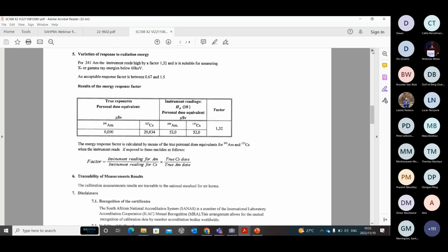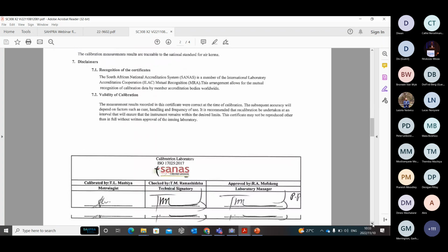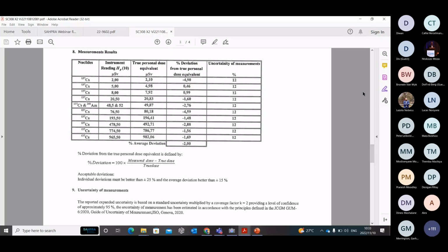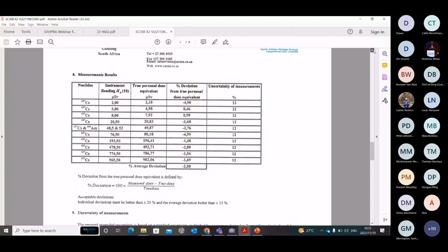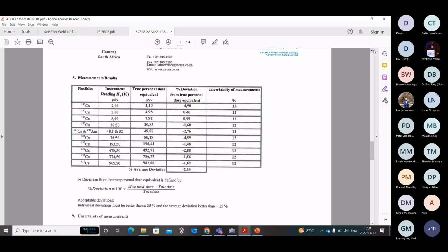Scroll to the next page, to the next table. Okay, thank you. Scroll a bit down. Thank you. This is more or less the same table that I presented in the results: the instrument responded 2 microsievert, and the dose given to the instrument was 2.1. The percentage deviation, that is the intrinsic error, is 4.90, and this is the uncertainty, which is plus or minus 12.